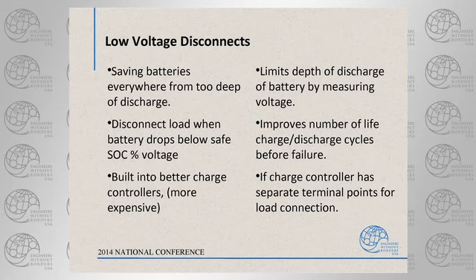Yeah. If they're not adjustable, you'll often find that they're very low. They're going to barely protect the battery, but you're still going to be able to deficit cycle over time. You're going to be at a 75% discharge or more. You're going to have reduced life if you're hitting that on a default on most charge controllers. So if you're in system design, now granted this is operation and maintenance, but if you're in system design, make sure you get a charge controller where you can set that protection voltage high enough that you get some life out of the batteries.